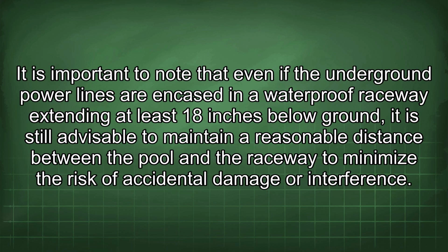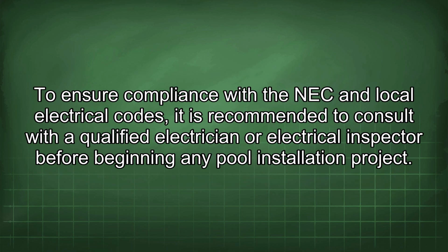It is important to note that even if the underground power lines are encased in a waterproof raceway extending at least 18 inches below ground, it is still advisable to maintain a reasonable distance between the pool and the raceway to minimize the risk of accidental damage or interference. To ensure compliance with the NEC and local electrical codes, it is recommended to consult with a qualified electrician or electrical inspector before beginning any pool installation project.